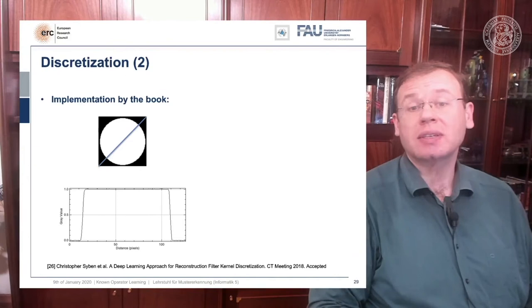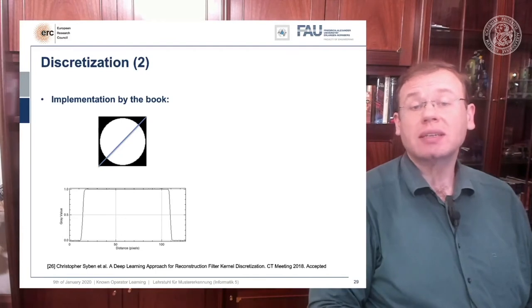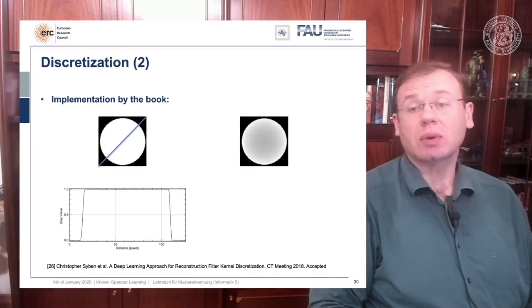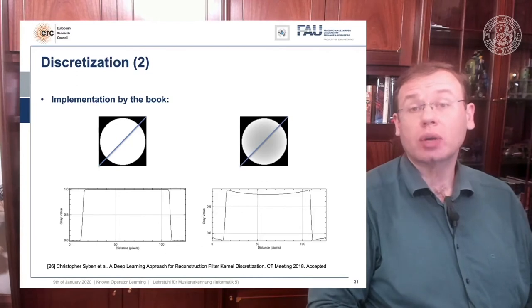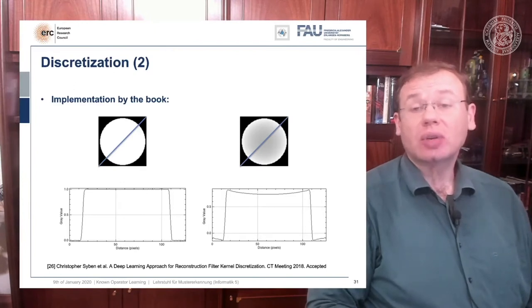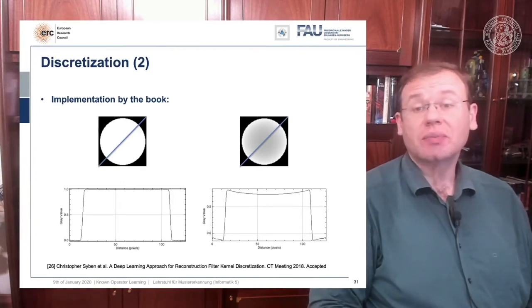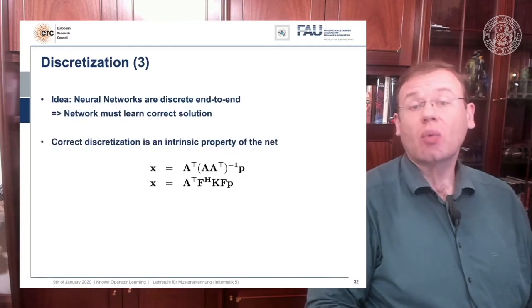Everything is one within the cylinder and outside of the cylinder it's zero. We're showing this line plot here along the blue line through the original slice image. Now if you just implement filtered back projection as you find it in the textbook you get a reconstruction like this one. A typical mistake is that you choose the length of the Fourier transform too short and the other one is that you don't consider the discretization appropriately.